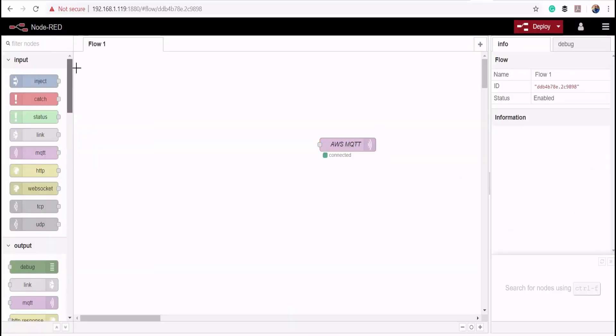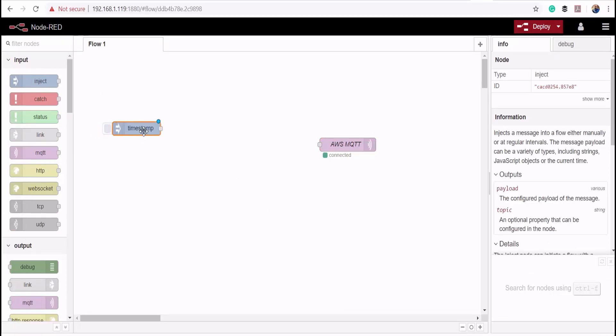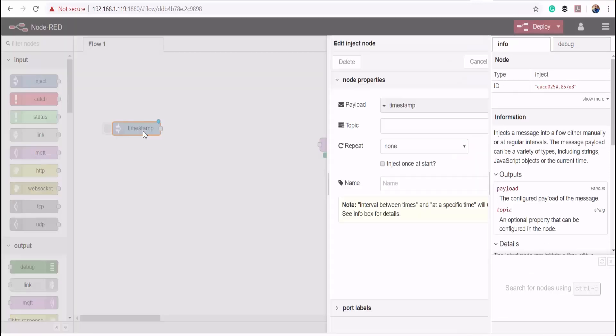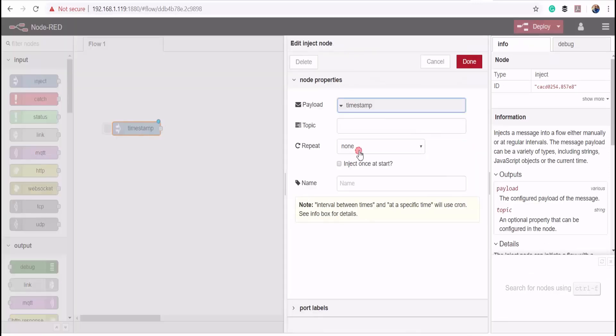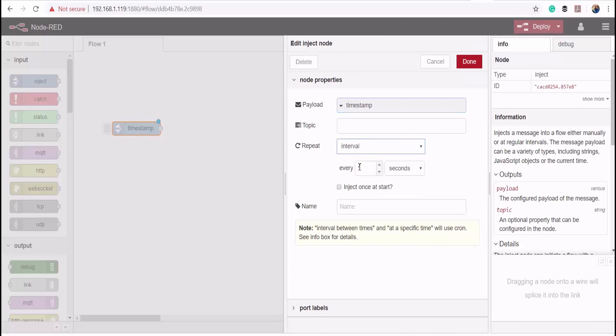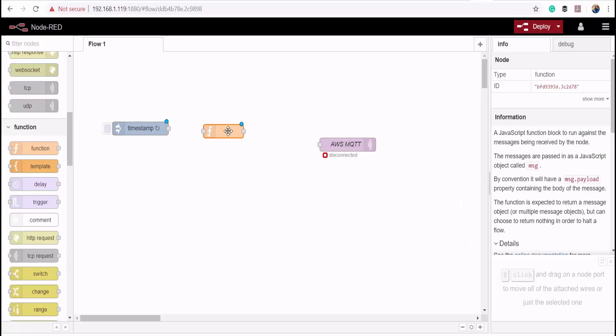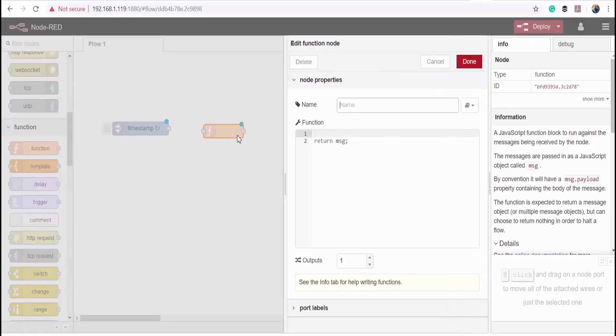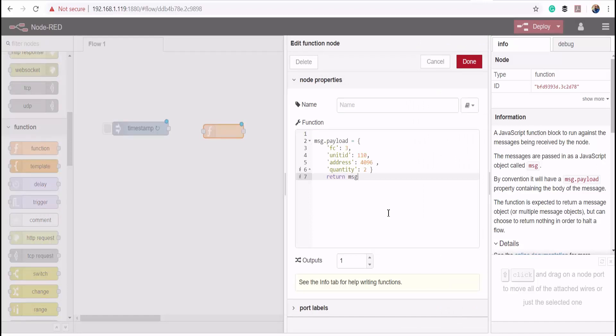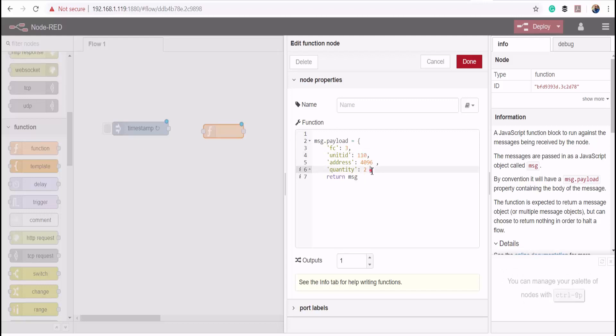Now I'll add an inject node and set it to publish data after every 5 seconds. Then I'm going to use a function block to prepare my Modbus message. I'll copy this object, which specifies my function code, unit ID, register address, and the quantity.